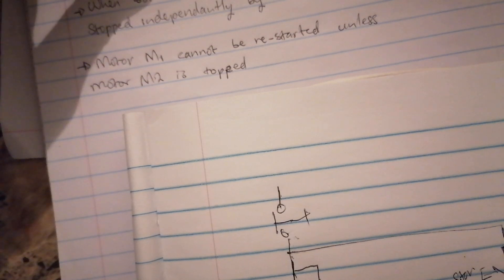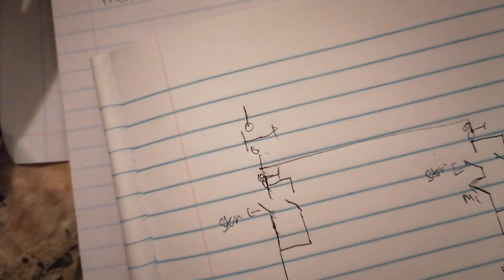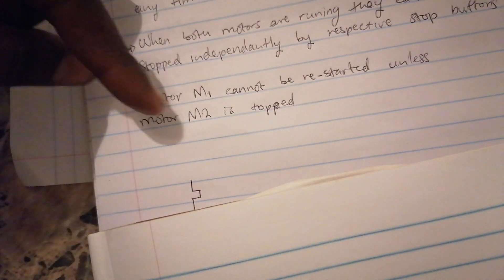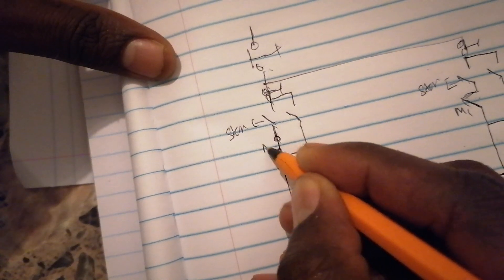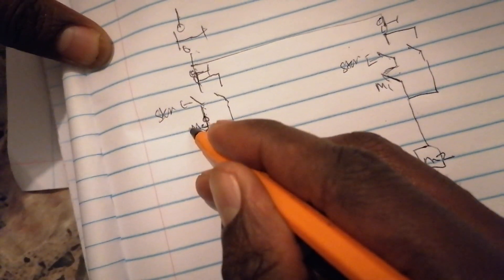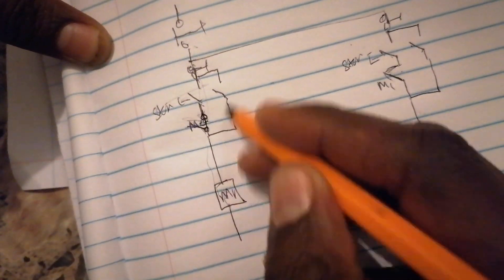When both motors are running, they can only be stopped independently, so you have a stop button each. The last statement said motor one cannot be restarted unless motor two is stopped. That means you cannot start motor one here - you have a normally closed contact for motor two. When motor two energizes, this one opens, so motor one won't start because motor two must first be de-energized.